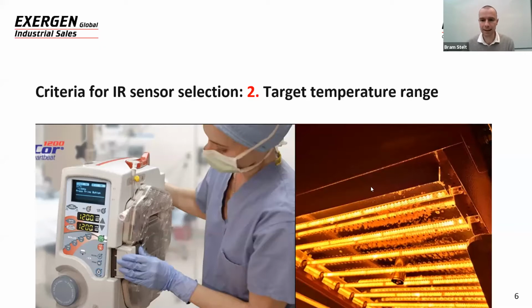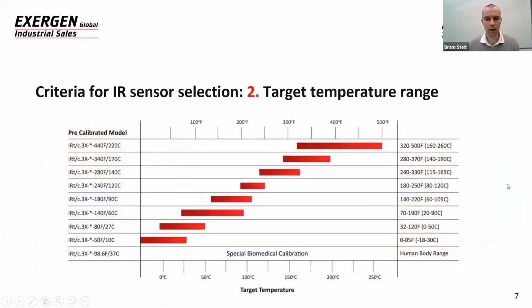So in the IRTC, we cover this by using various temperature calibrations. The IRTCs are nonlinear, and in these calibrations, we put the nonlinear signal on top of the linear signal. So in these ranges, in the red bars, this is where an IRTC is within 2% linear of a standard thermocouple signal. So for the various applications, you need various temperature ranges. For instance, the 180F90C is most accurate between 60 degrees Celsius and 105 degrees Celsius. So with this, you can cover the multiple temperature ranges that are required in the field. For higher temperatures, we have the adjustable modes.